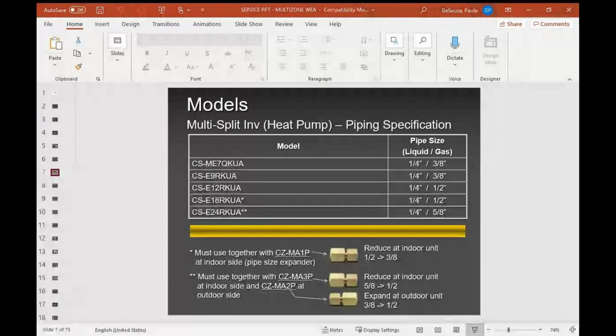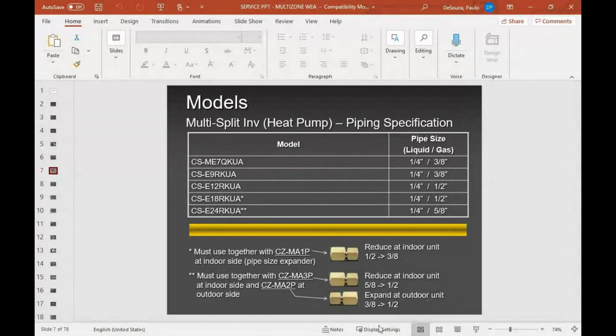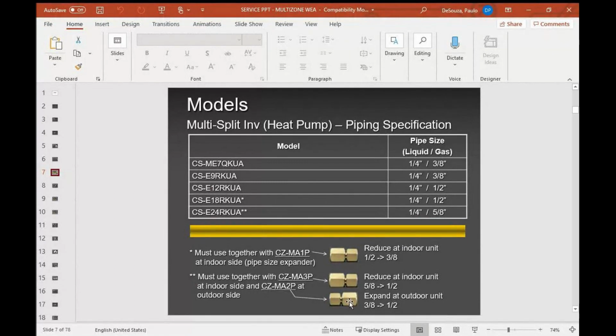So basically, I was explaining to you about the difference between our multi-zone and our competitors. I know most of our guys install other manufacturers, and with other manufacturers, they only use the adapter at the outdoor section. Okay, guys? In our case, it's not the case. It's different. You have to use 3/8 and quarter at the outdoor unit. All the ports, all the service ports, the suction and the liquid line are 3/8 and quarter. 3/8 suction, 1/4 inch liquid. You run those size pipes all the way to the indoor unit. And if the indoor unit is, let's say, for example, in this case, a 12,000, then you use an adapter to upgrade or upsize it to 1/2 inch.